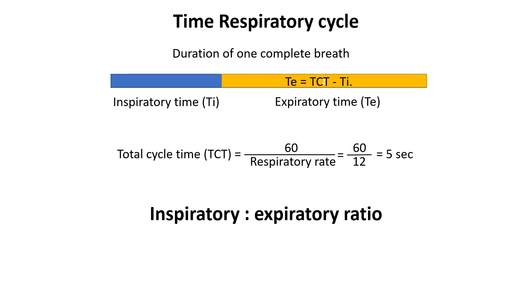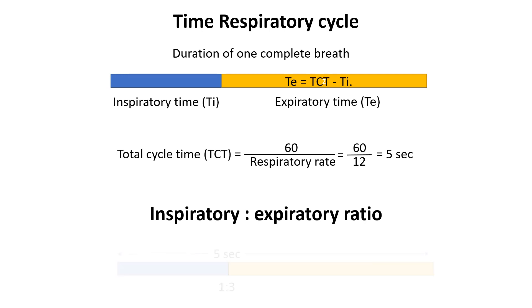Using the same example with a total cycle time of 5 seconds and an IE ratio of 1:3, the inspiratory time is 1.25 seconds and the expiratory time is 3.75 seconds. Depending on the mode of ventilation, inspiratory time is set through various methods, though respiratory rate determines the overall breath cycle time.